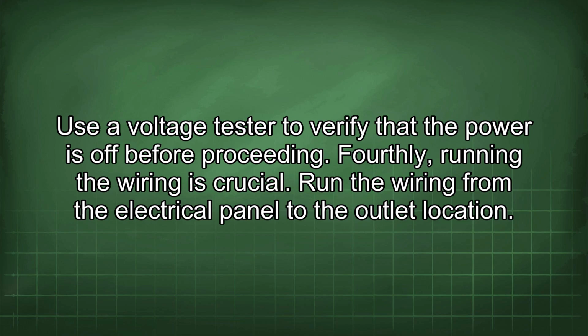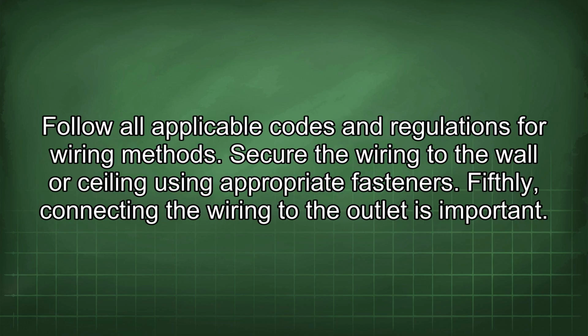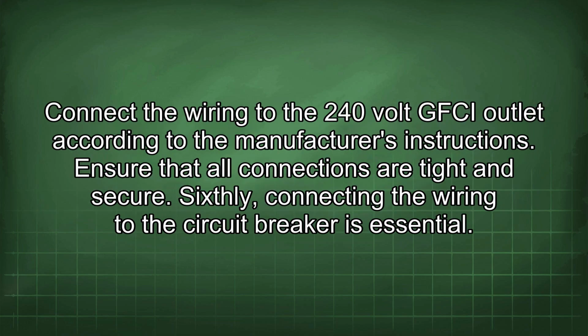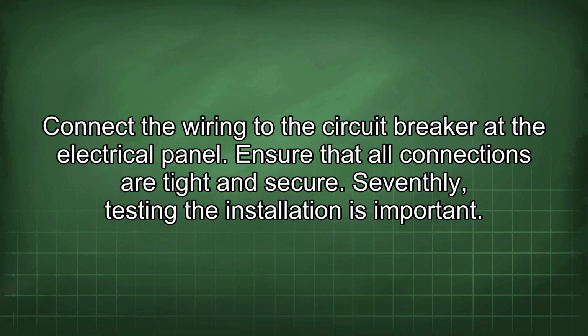Fourthly, running the wiring is crucial. Run the wiring from the electrical panel to the outlet location. Follow all applicable codes and regulations for wiring methods. Secure the wiring to the wall or ceiling using the appropriate fasteners. Fifthly, connecting the wiring to the outlet is important. Connect the wiring to the 240-volt GFCI outlet according to the manufacturer's instructions. Ensure that all connections are tight and secure. Sixthly, connecting the wiring to the circuit breaker is essential. Connect the wiring to the circuit breaker at the electrical panel. Ensure that all connections are tight and secure.